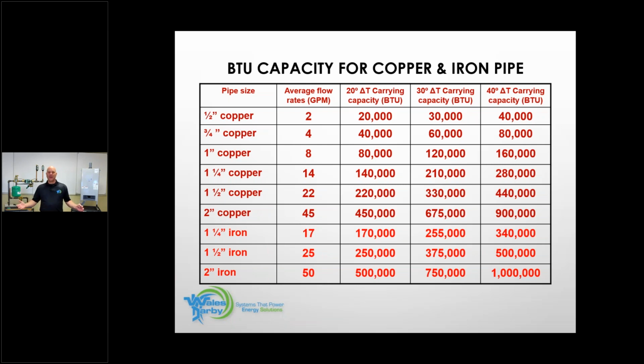The speed limit on the New York State Thruway is 65. That's best practice. I'm not telling you to do 65. I'm not telling you to do 55. I'm giving you best practice. That's what this chart is. If we average those flow rates, that is the BTU you will move through that pipe. You can go find another chart that will give you a number that you may want to see.